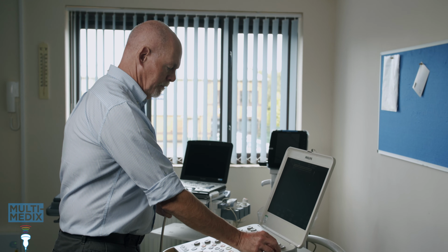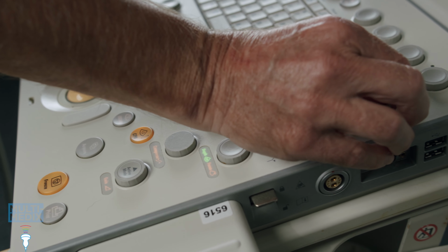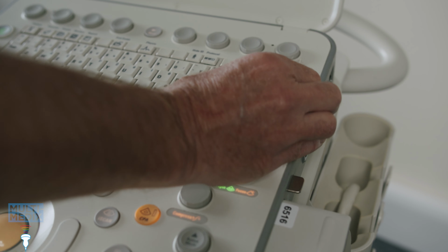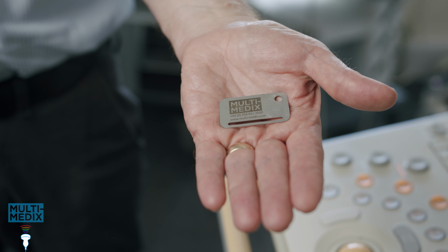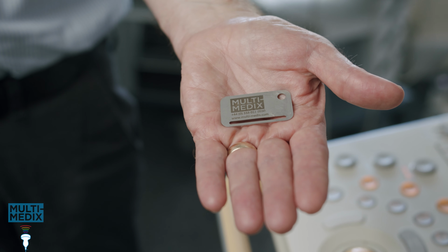Don't forget to check TGC, as that's one control that won't have been included in the preset unless it's a touchscreen control. We can't see dropout in the in-air reverberation due to beam steering, so we have to turn that off by using M mode with the M line central. Now we can look for any dead elements using a paperclip or a test tool like this. If the tool's placed across the array, because it has a narrow edge, it's in contact with a very small area that could be as small as a single element.